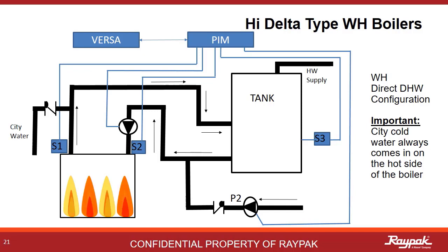Moving on from hydronic and into WH-type appliances, as in water heaters. When a high-delta is purchased to be a water heater, there is only one mode of operation, so the plumbing is more specific. Here is a drawing for a water heater application. Important note: city cold water always comes in on the outlet side of the boiler to be mixed with the hot water the boiler is producing on the way to the tank. Introducing city cold water on the inlet side of the boiler will likely lead to going below the required minimum inlet temperature of 105 degrees Fahrenheit, resulting in condensing in the boiler.